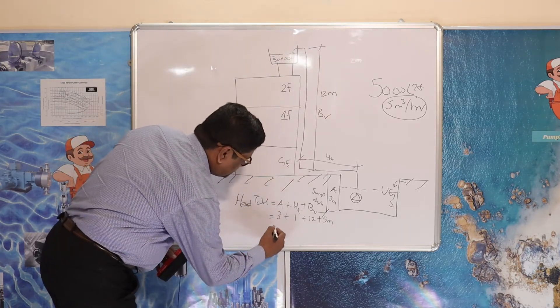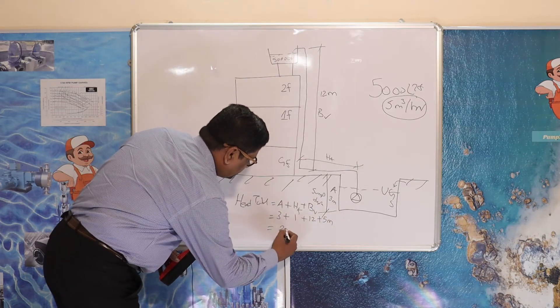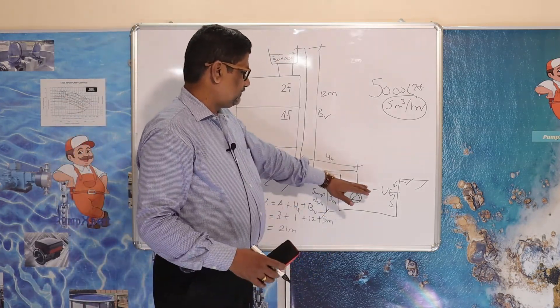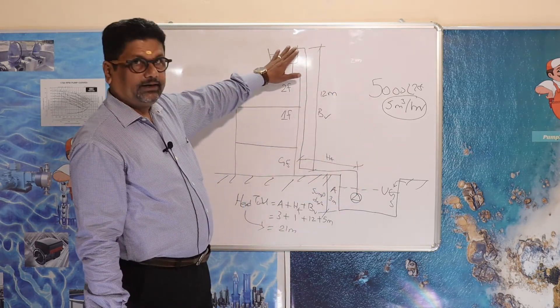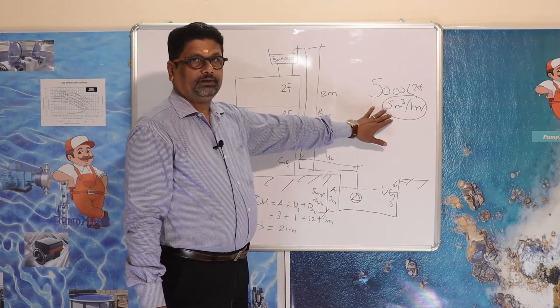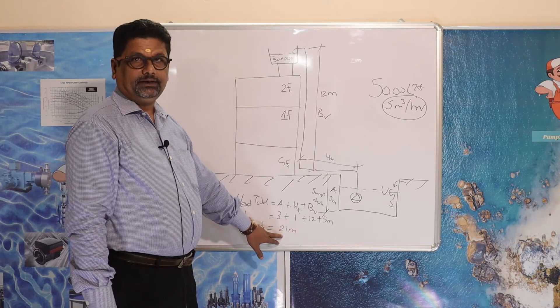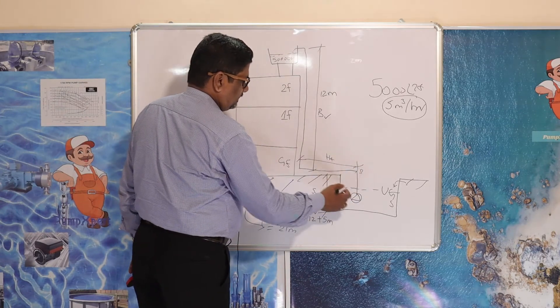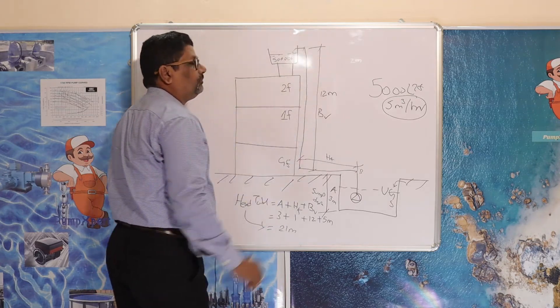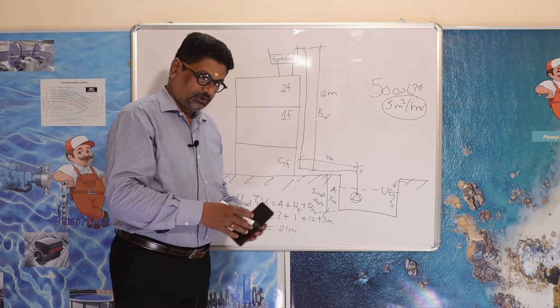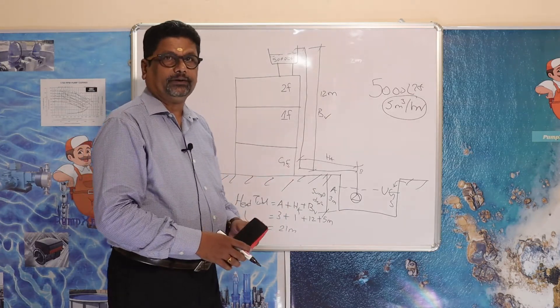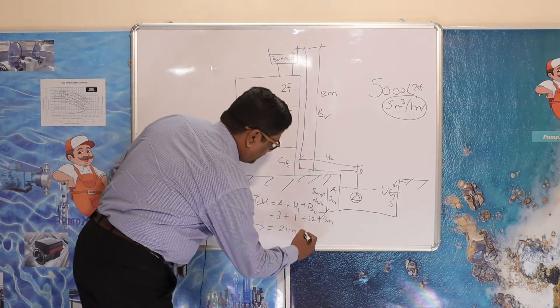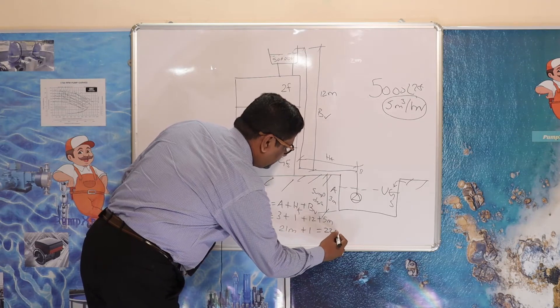When I put it all together: A is 3 metres, plus friction loss of 1 metre, plus 12 metres vertical, plus 5 metres pressure — that gives 3 + 1 + 12 + 5 = 21 metres total head for the pump. Then accounting for bends — I have about 4 bends — the additional friction loss adds roughly 1 metre more, giving 22 metres total head.